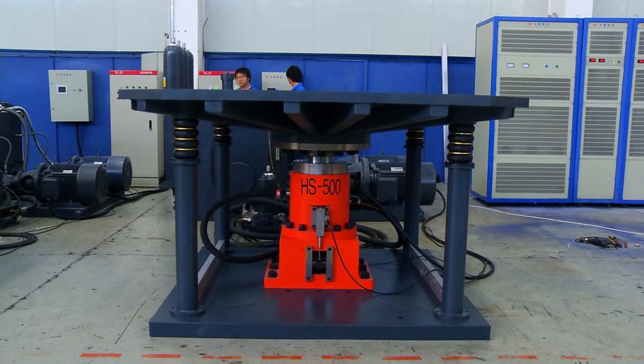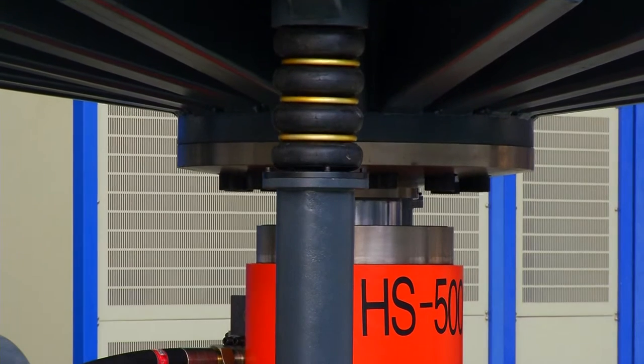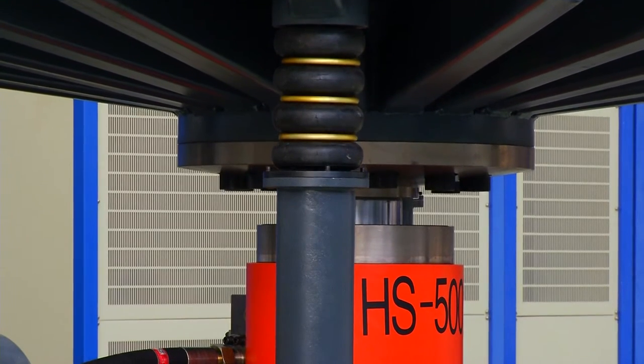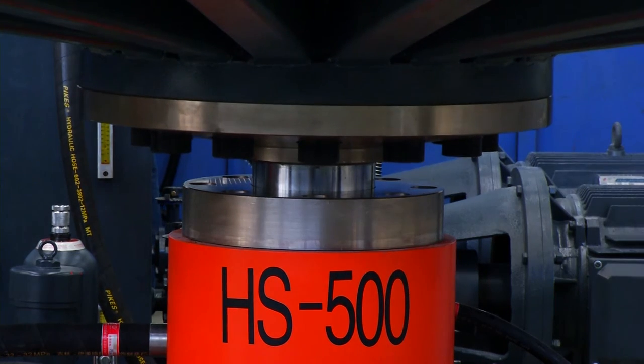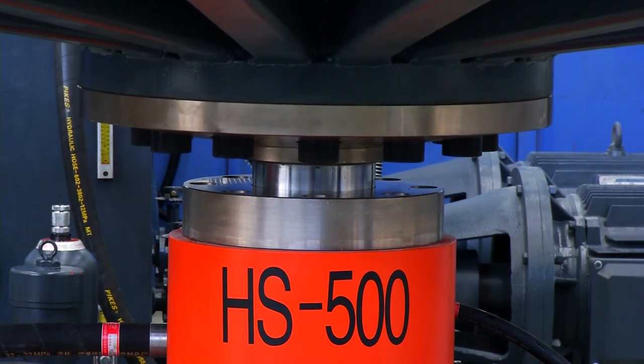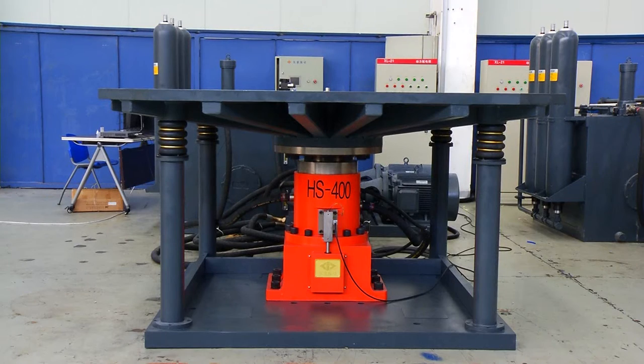It also can be integrated into production line as a subsystem, controlled by host computer to achieve online operation. The maximum force of this system is 500 kN and the maximum payload is 20,000 kg. This system has explosion-proof function and remote control over 1,000 meter distance which is safe and reliable.